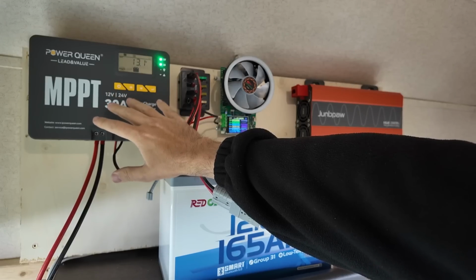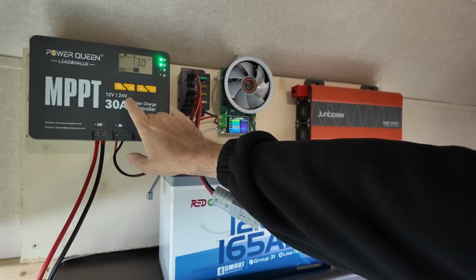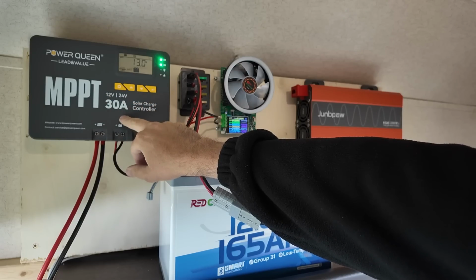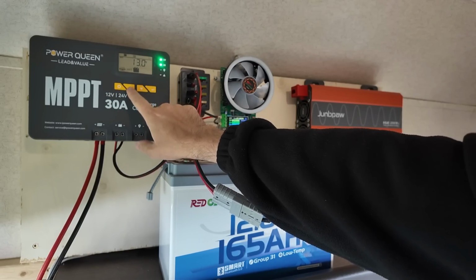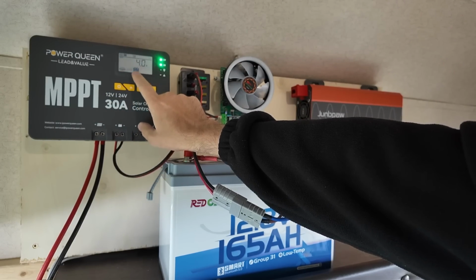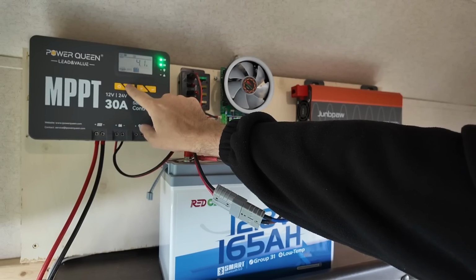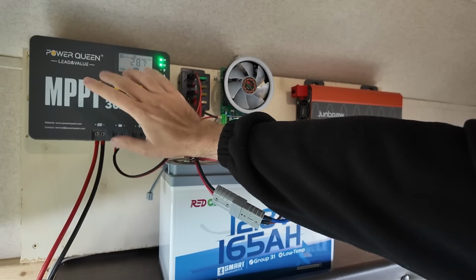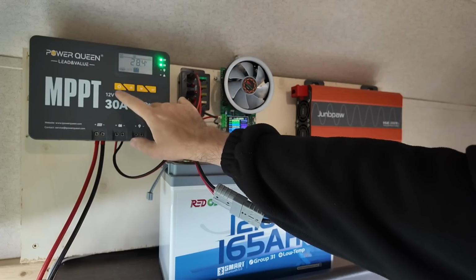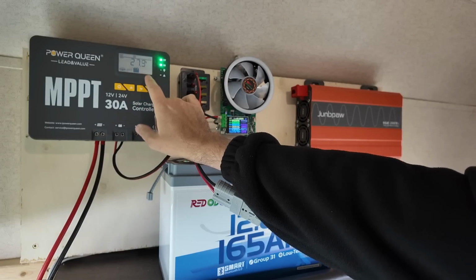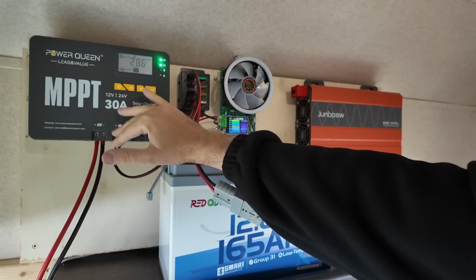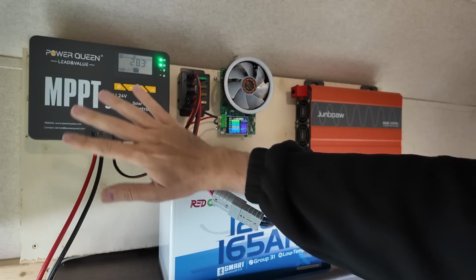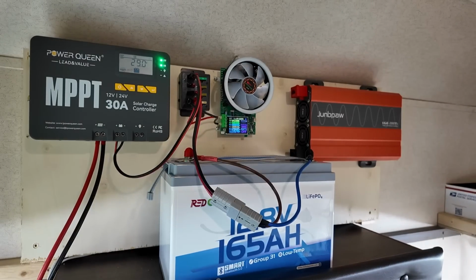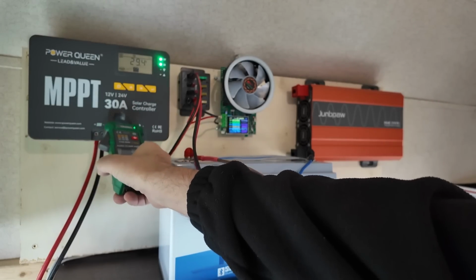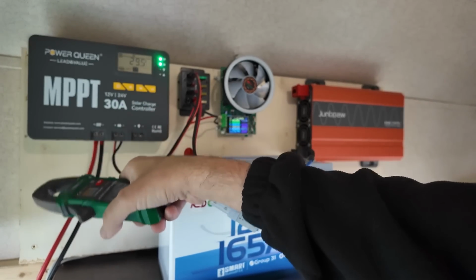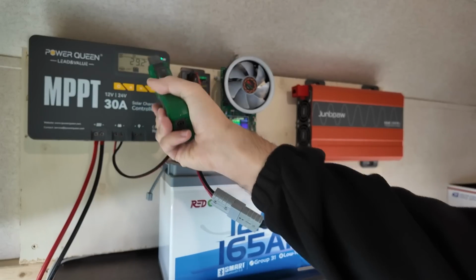If you do some quick math, 400 watts of solar at 24 volts rated will tell you how many amps the solar panels can produce. But we can do some stuff here. This is telling me that I'm getting 4 amps from the lousy solar conditions I showed earlier, 28.8 volts, 29 volts - and that's the thing about all of this voltage stuff. 24 volt panels have a 32 volt open circuit, so they're going to do somewhere around 24 volts plus or minus. None of these numbers anywhere in this sequence are going to be 100% exact. So when it says 30 amps, you're going to get 30, 31, 29 - it depends on the sun. You might even get down to 4, like we're getting today.